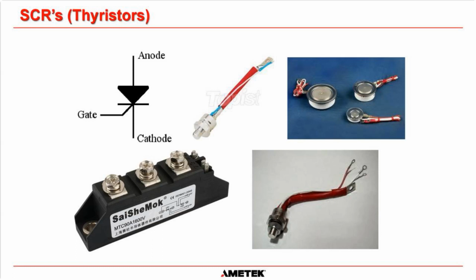What I will say is, for a rectifier bridge, let's start off with a single phase, fully controlled bridge. That is going to reflect a huge amount of harmonics back onto the supply system, because it's only switching basically twice every 60 hertz, and that switching will be reflected back onto the supply system. For a three-phase system with 6 SCRs, it's not as bad, but the harmonics are still enough there that you have to think about the design of your charger and whether it is suitable to connect to your supply system.